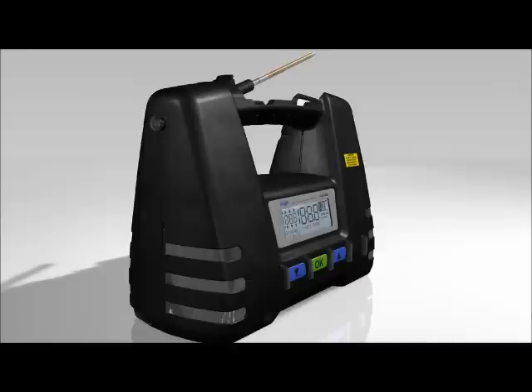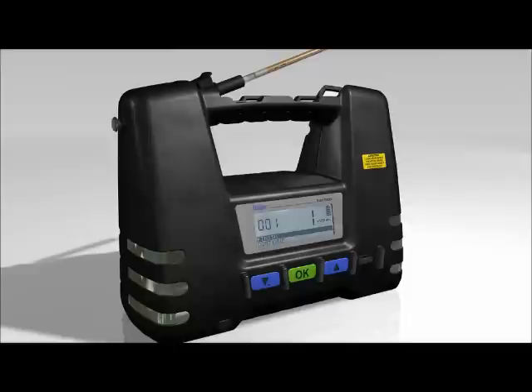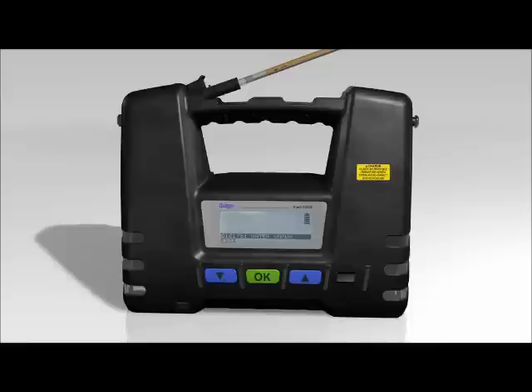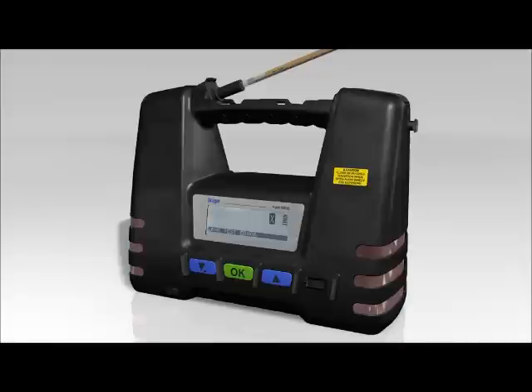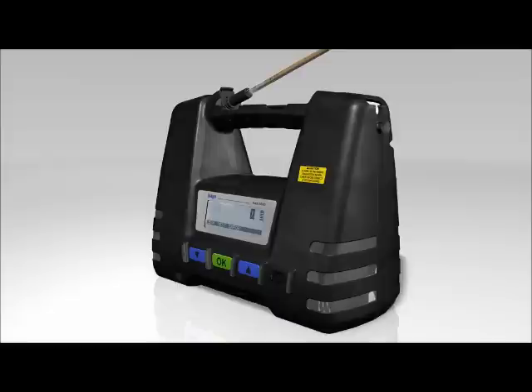To the left and right at the bottom of the tube pump are the LEDs. Flashing green means the measurement is complete, and the LEDs will keep flashing until the OK button is pressed. If the LEDs flash green twice, the barcode has been correctly scanned. If the LEDs flash red, an error has occurred. To deal with the error, read the error code or message in the display and check all connections, measuring parameters and tubes.